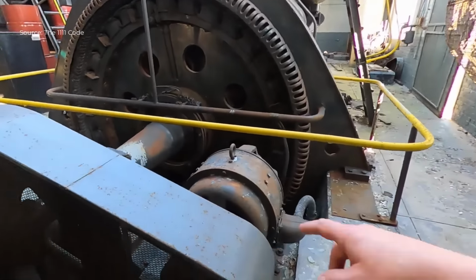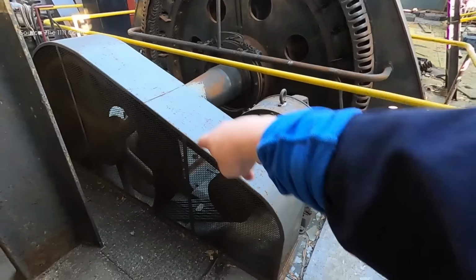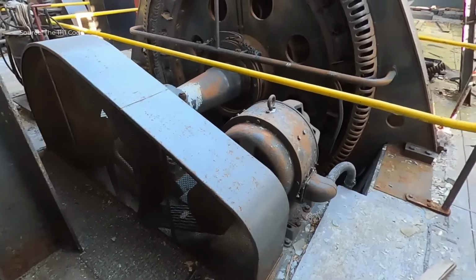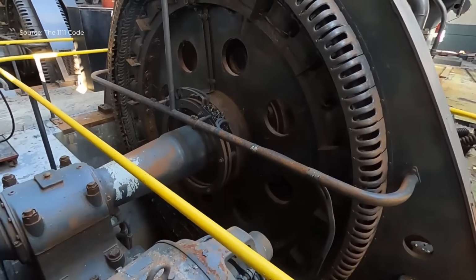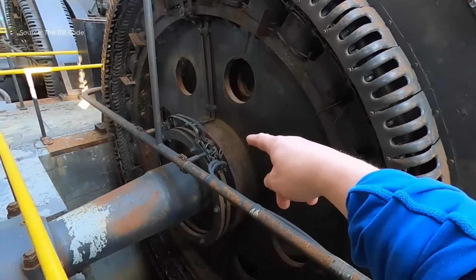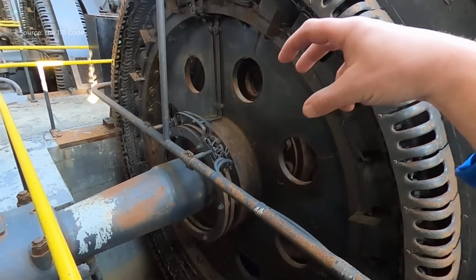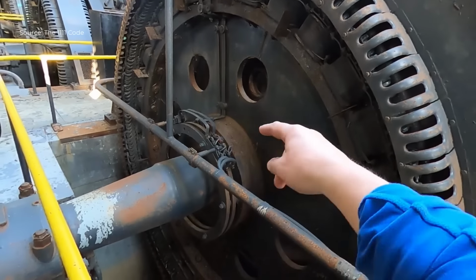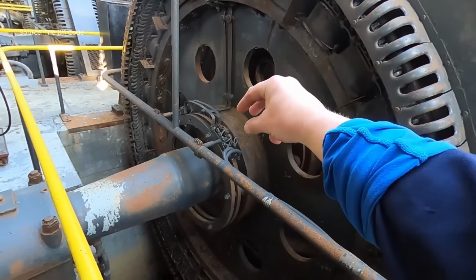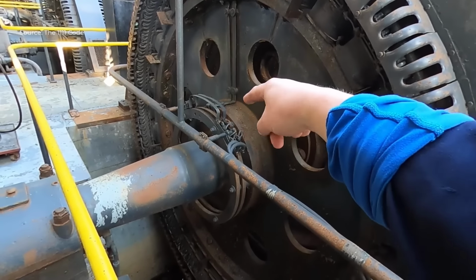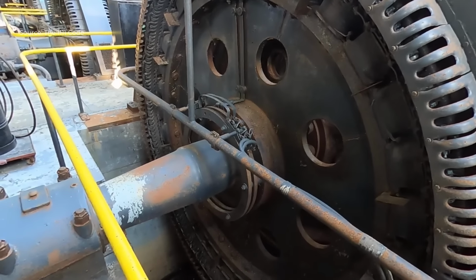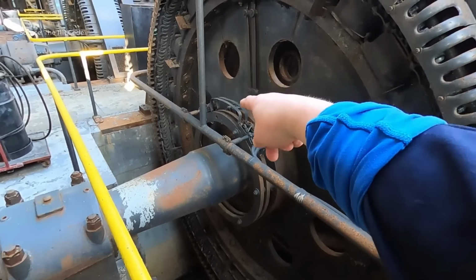One of the most fascinating features of the generators is their salient pole design. Each generator uses magnetic poles energized by direct current, supplied through slip rings and carbon brushes. A smaller auxiliary generator, mounted on the same shaft, provides this excitation current, allowing operators to control the output voltage by adjusting the magnetic field strength.